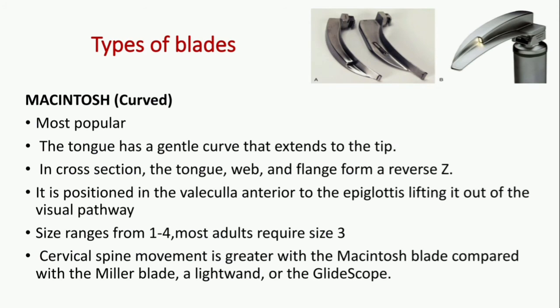The most popular blade is the Macintosh. The tongue has a gentle curve that extends to the tip. In cross-section, the tongue, the web, and the flange form a reverse Z. It is positioned in the vallecula, anterior to the epiglottis, lifting it out of the visual pathway. The size ranges from 1 to 4 and most adults require size 3. Cervical spine movement is greater with the Macintosh blade compared with the Miller blade, a light wand, or the Glidescope.